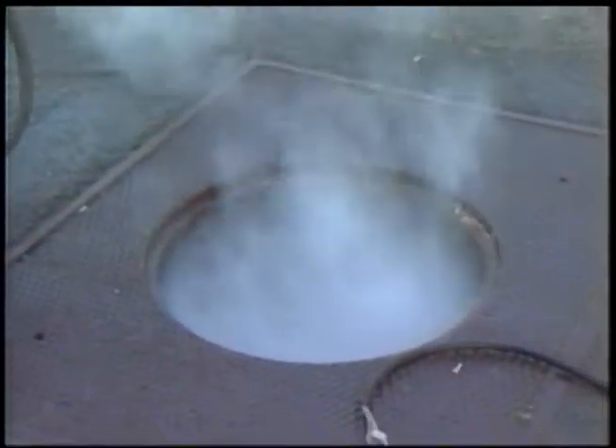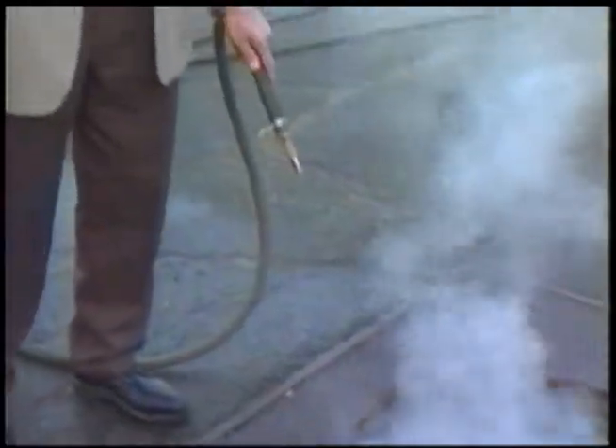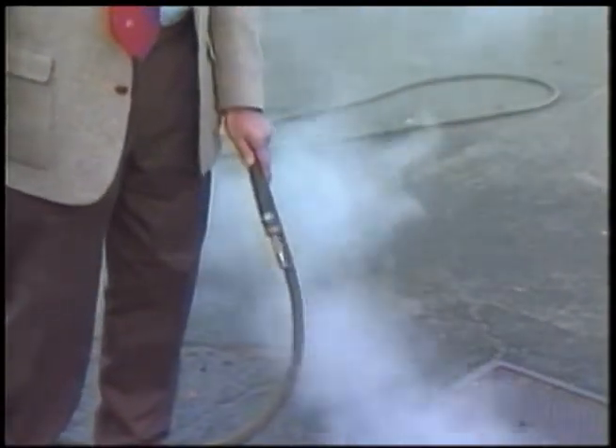What we just showed you is that a 15,000 volt fault in a manhole with trash burning and the fault still active and the cable energized, you can put it out with a hose, with water, even as simple as a garden hose.